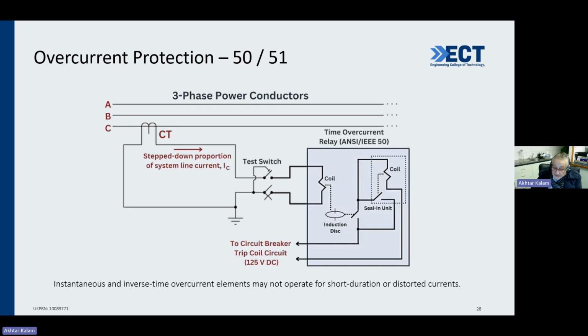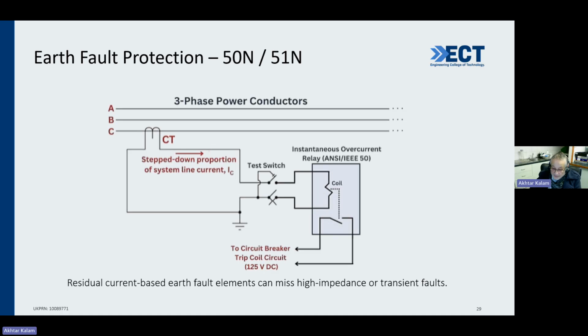And you find that inverse time overcurrent elements may not operate for short duration, or, as I've shown you, the current was distorted. And this is a very big problem. So sometimes you will have to use something else. The circuit breaker coil did not operate. So I go to my next device, which is an earth fault protection. This one is a 50N, 51N, N is for neutral. This is a time overcurrent protection, and this too does not operate for short duration or distorted currents.